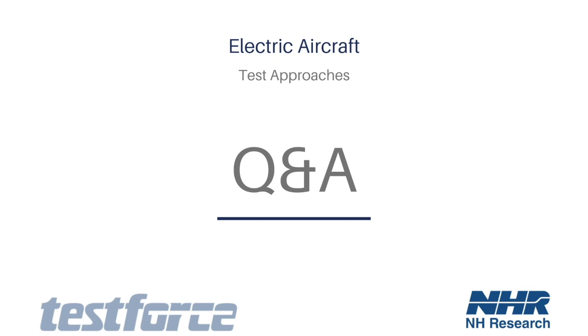Good question. We're seeing a lot of different technologies out there. Most commonly, what we're seeing today is a glycol-based coolant. That's very common for automotive, like the cooling system in your radiator today. That's usually pumped through the battery, through cooling plates, and in testing, there are some people we've used in the past that make those glycol temperature conditioners. Those can interface with our test executive as well. So if you want to emulate those temperature conditions through the cooling system, you could do that as well.